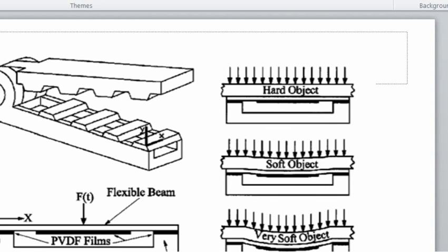When a force causes stretch in the PVDF film, a polarization change occurs and voltage signals are generated. The magnitude, position, and distribution of the applied force can then be determined by measuring the amplitude of the output voltage at all electrodes and comparing such quantities among them. This sensor exhibits very high sensitivity and good linearity. A high signal-to-noise ratio over a measurement range of 2 Newton was also achieved with this design.